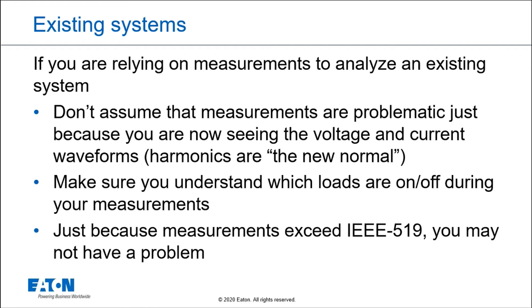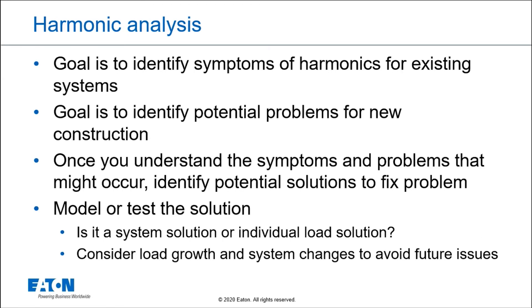For existing systems, if you're relying on measurements to analyze an existing system, don't assume that the measurements are problematic just because you're now seeing significant voltage or current distortion. Remember that harmonics are the new normal — you're going to see a lot of really interesting waveforms, but it's not necessarily problematic. Make sure you understand which loads are on and off during your measurements, and just because you may exceed the IEEE 519 limits doesn't necessarily mean that you have a problem. Those limits are recommendations and guidelines for trying to understand if you're going to have problems.